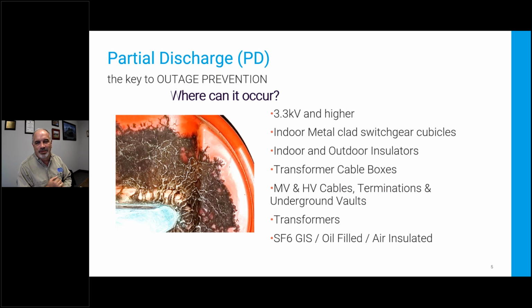Where it's real common is metal-clad switchgear, both indoor and outdoor, transformer cable boxes, cable terminations, underground vaults. Cable terminations is probably the most likely area for it, and then indoor outdoor switchgear where you have the high humidity because you've got some outdoor component is real common as well. It can occur in any kind of insulation, whether it's air, oil, SF6, whatever you got.